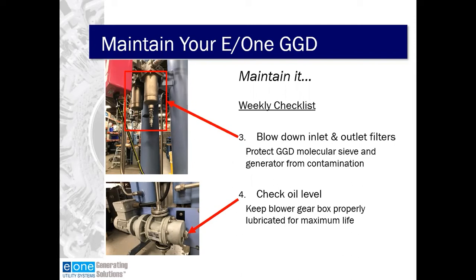The last weekly check is to ensure that the appropriate level of oil is in the gearbox. There's a sight glass on the hydrogen circulator on the gearbox side. The oil level should be about 50%. If there is a need to add oil, at that point you would follow the procedure in the manual to do that safely. And as we walk through these checklists, as Rachel noted at the onset, we do have a training video that we've prepared for you. Upon completion of the class, the training video will be made available, and additional details associated with these procedures will be available in that video.